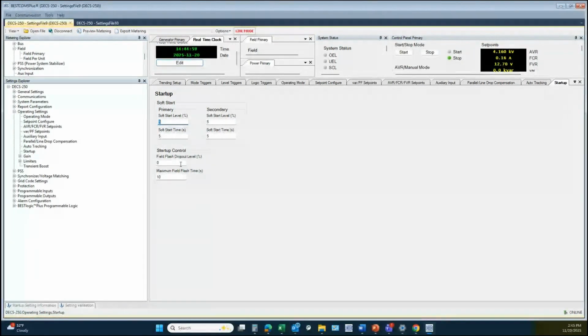Startup control, this is if you're using the DECS to control your field flashing circuit. If the DECS is getting operating power from the generator output being shunt powered, then you may need field flashing at some point. And this is where you would define what the percent of rated voltage would be that you want to drop out the field flashing, and then the maximum field flashing time so you don't field flash for too long and cause damage. If you don't reach the field flash dropout level before the time expires, you will end up with a fail to build alarm within the DECS.